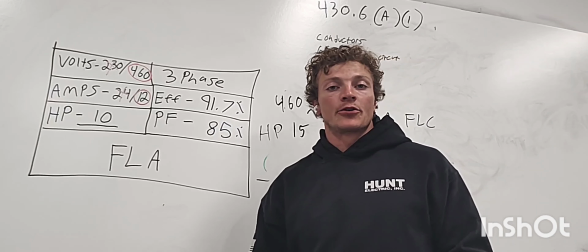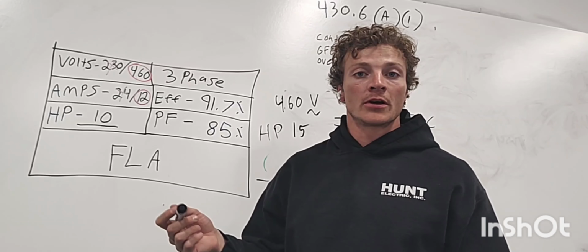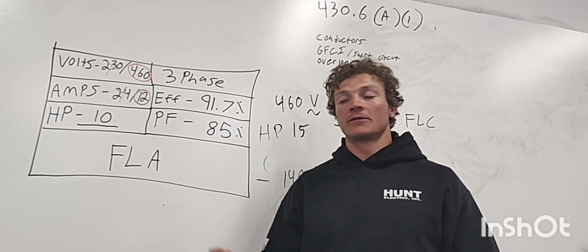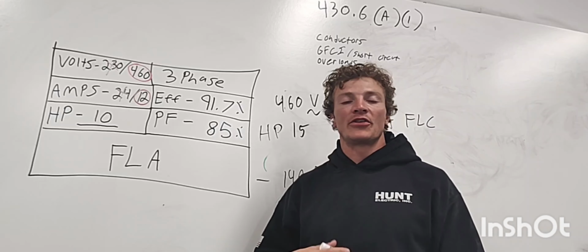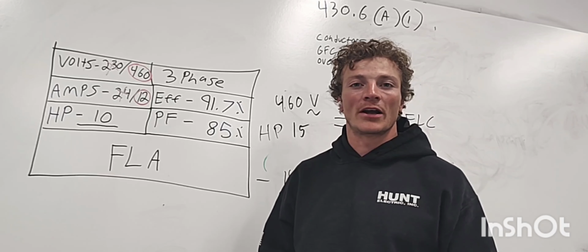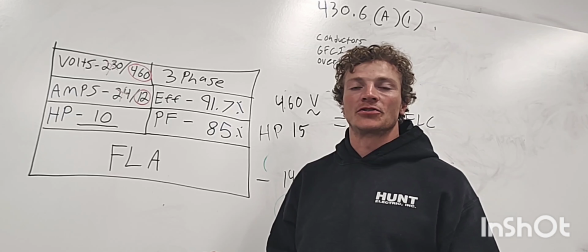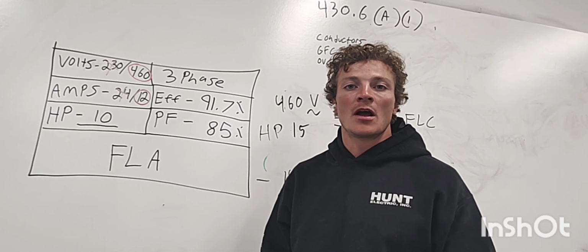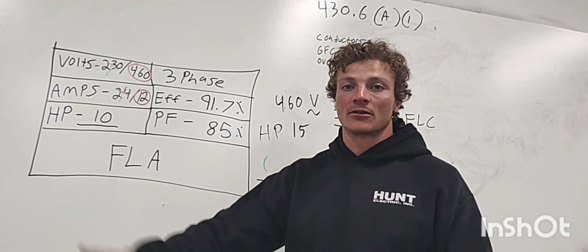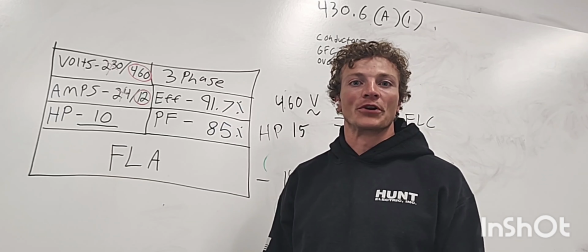Alright, so that is how you size the conductors for a motor, and that was a real life example of us doing it. I think in the field we're actually going to pull 10 wire just to be safe and just to account for voltage drop, but we could get away with 12 wire. The panel is, I think, like 40 feet from it.